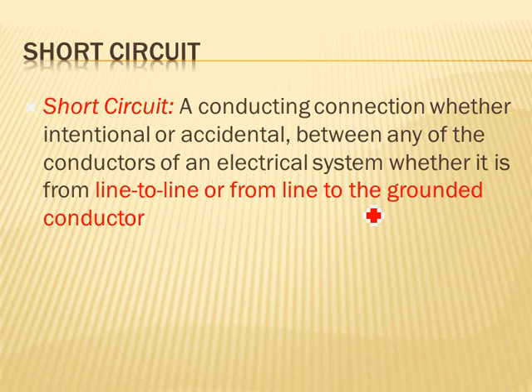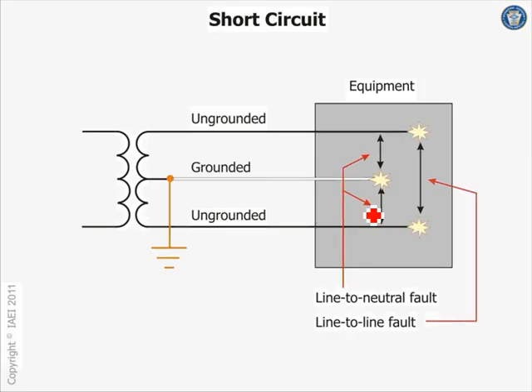If you have a phase to the enclosure, that's a ground fault. So all these are considered a short circuit: phase to neutral, not the equipment grounded conductor, not the frame. That confuses people. Why do you think a phase to neutral fault is a short circuit? Because that grounded conductor is part of your short circuit. So really, the equipment grounded conductor does not do you any good. It doesn't interfere. If you have a short circuit between a hot and a neutral, the current will go right through the neutral. It doesn't have a free ride over the equipment grounded conductor.